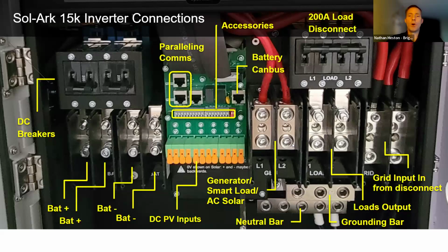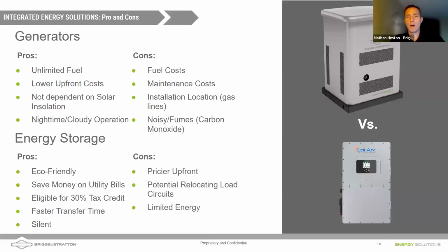Okay. Alternatively, you could bring AC coupled solar in there. So you could bring in 240 volts of maybe Enphase microinverters or a SolarEdge inverter that's already existing on a site. And so you can use this generator port for other things. We're going to be talking about using it as a generator port. But if you already have AC coupled solar on a house, you can use the Sol-Ark to control that and keep it active even in a grid outage. So we'll get to that.